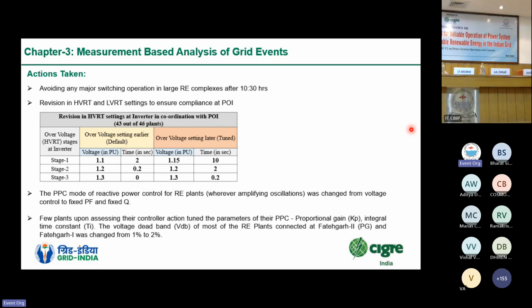So always there is a difference between the terminal voltage and the voltages at the point of interconnection. So we asked plants to modify their settings appropriately so that they are able to display the ride through behavior when the voltages at the point of interconnection go to the extremes. So you can see in the table also that we modified the ride through setting requirements. We gave the recommendation to modify their settings, and certainly some plants cooperated and the settings were modified. In some cases, the voltage limits were increased, and in some cases, the withstand time was also increased. So in some plants, whenever we observed the oscillations, we identified that their voltage controllers were not helping to mitigate the oscillations, rather they were magnifying the oscillations.